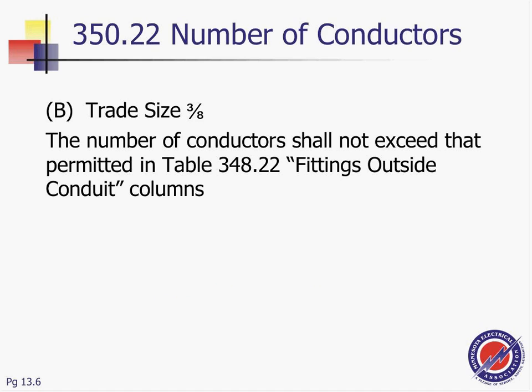Let me bring you to this slide that you only need to remember for the journeyman exam, because that's how they want to trick you. So 3/8 inch. If you go to NEC, you're not going to find it. If you go to Chapter 9, Table 8 or Table 2, you're not going to find it. They want you to go to a flexible metallic conduit table. This is a flexible metallic conduit table. They're referring you, for Liquidtight, to the table in flexible metallic conduit.